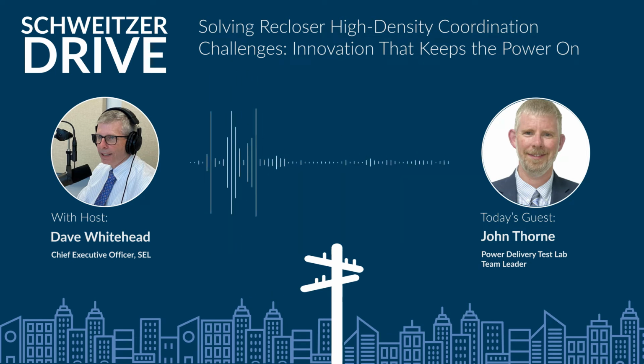Each recloser only has to talk to its adjacent recloser, the reclosers adjacent to it, and they share with each other whether or not they saw the fault. Each recloser then makes a good decision about whether it needs to trip fast or slow down and wait for somebody else to clear the fault, to interrupt the line. So it's this elegant complexity, if you will.